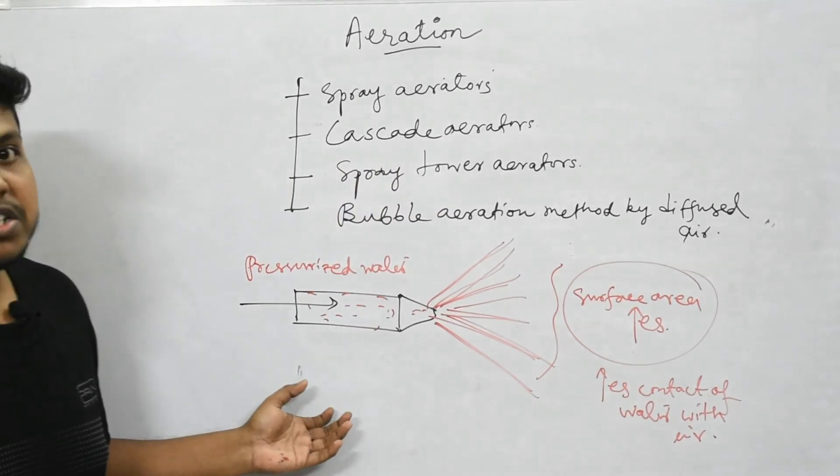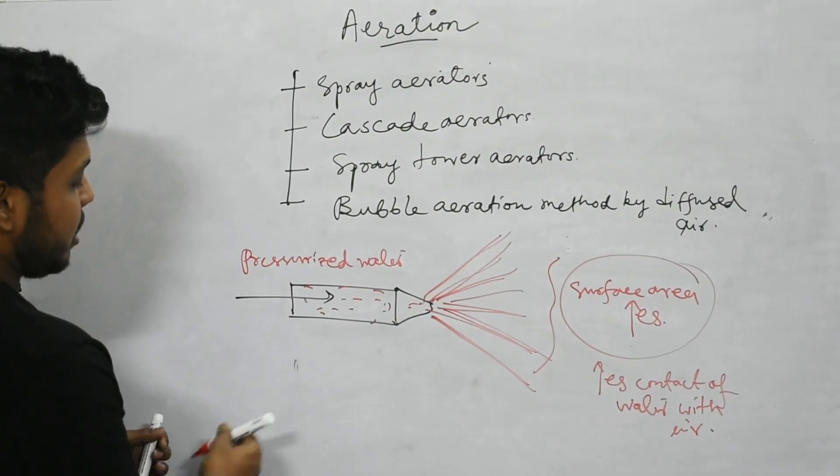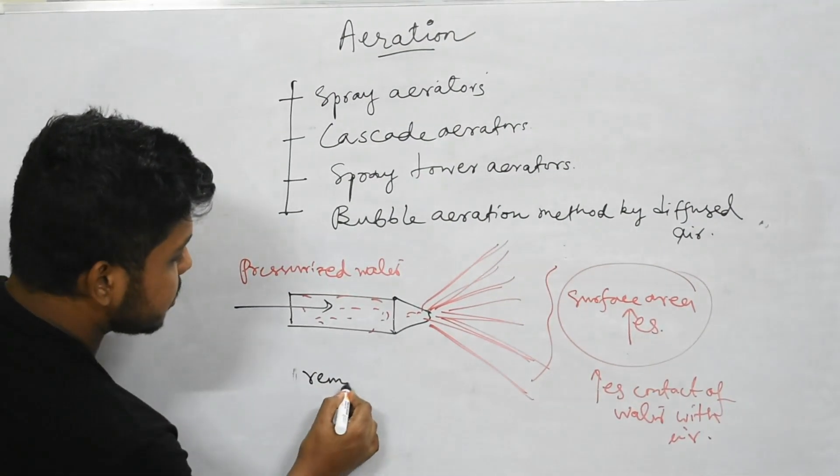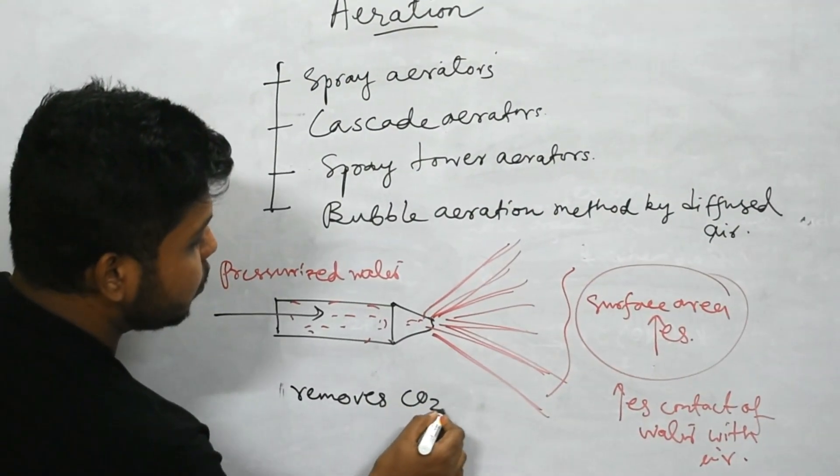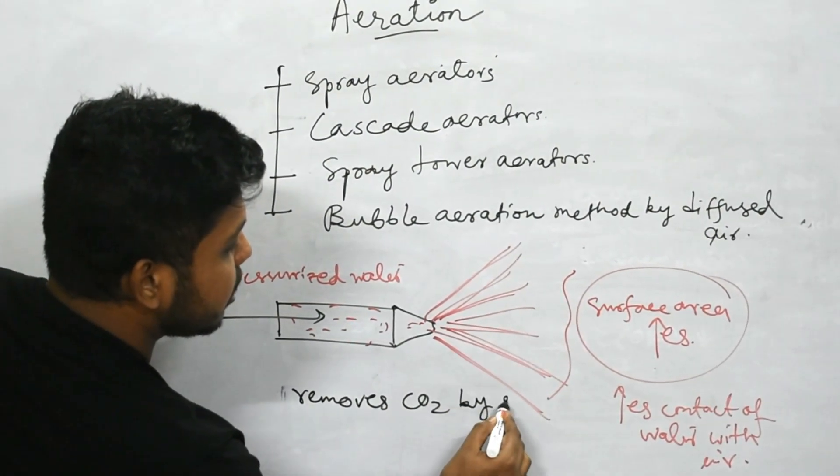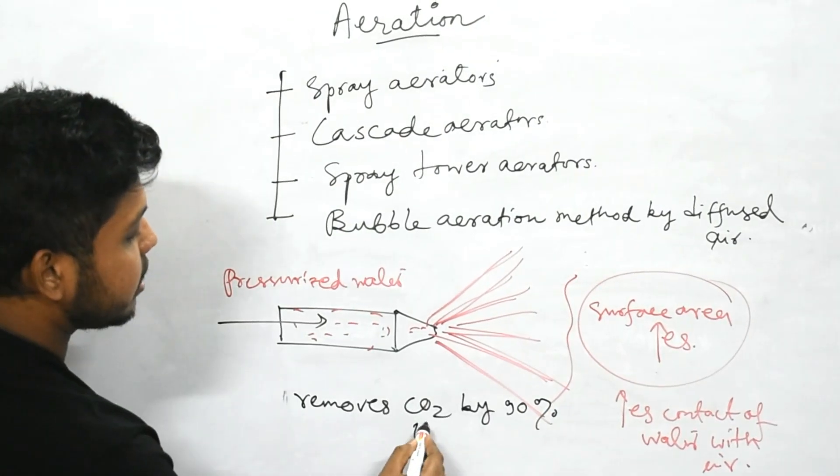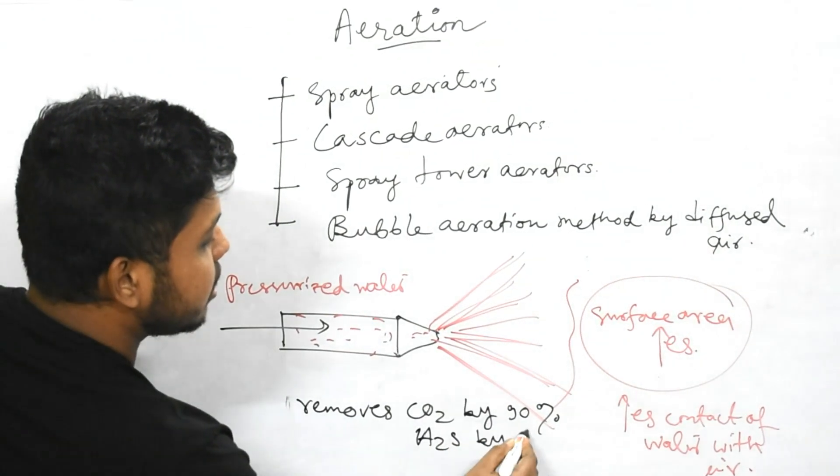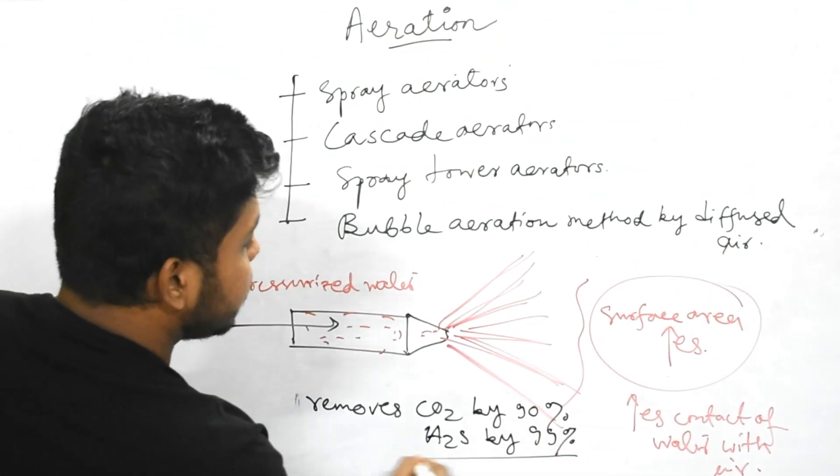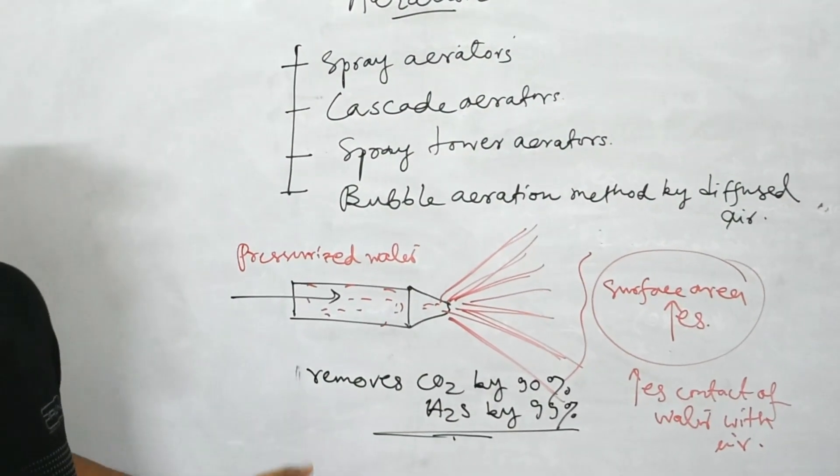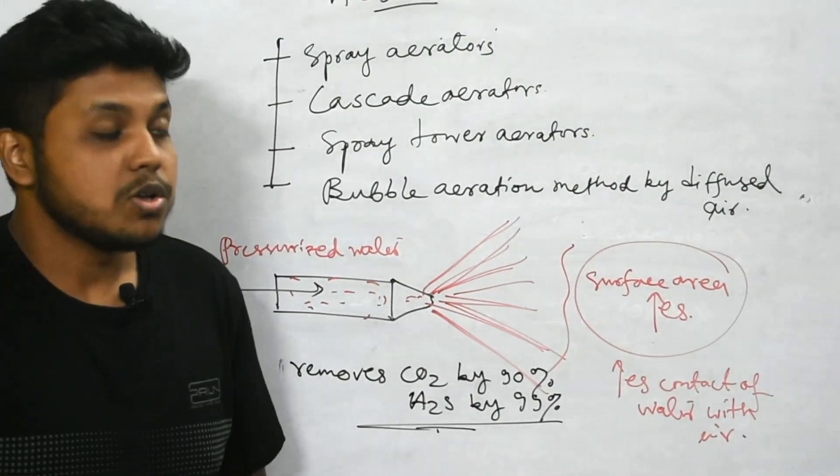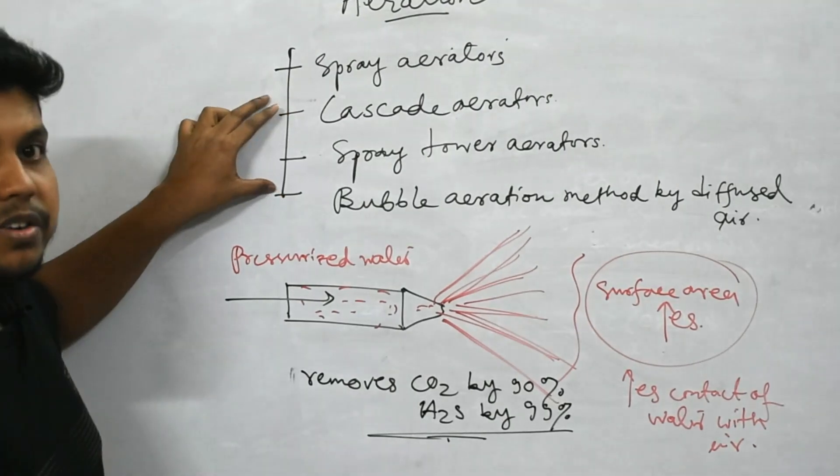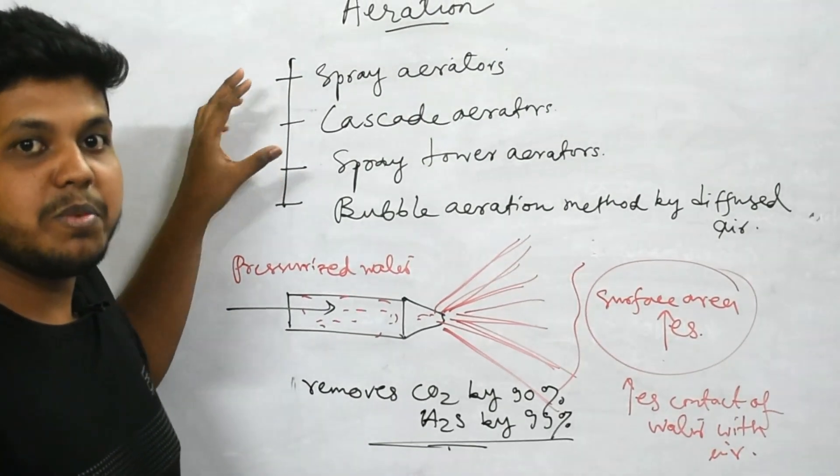The advantage of using spray aerators is it removes CO2 by 90% and H2S by 95%. This is the advantage of having these aerators. We will discuss the rest of three aerators by pictorial representation.